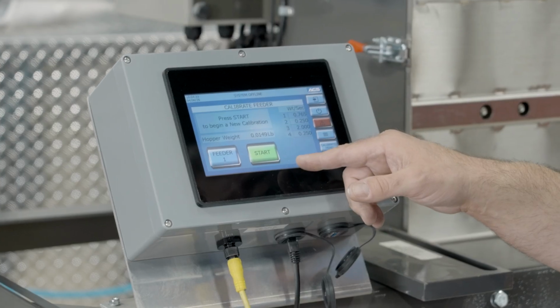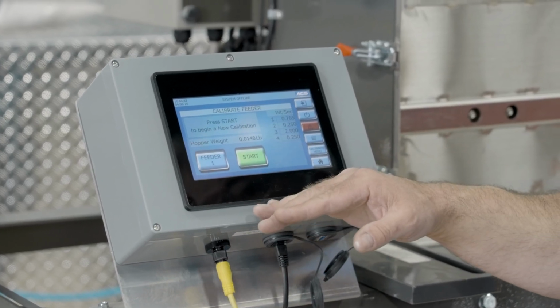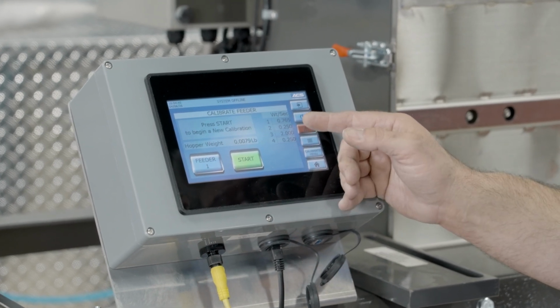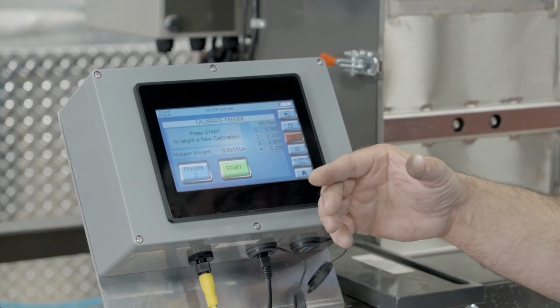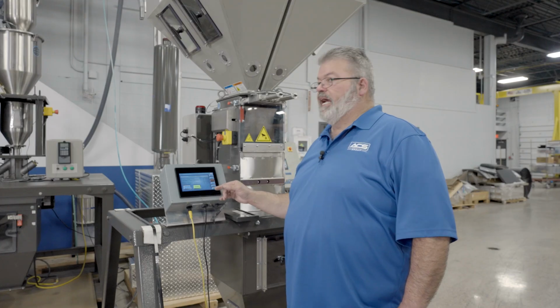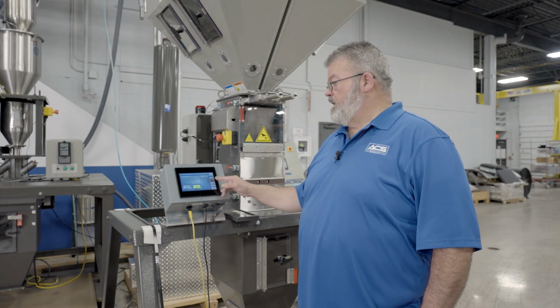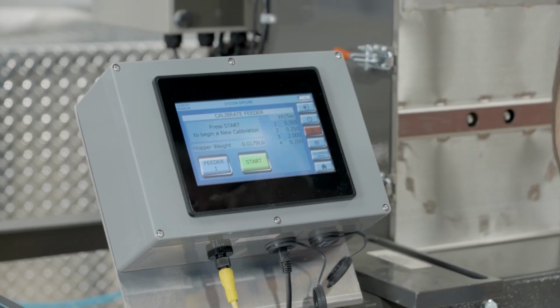That's how we basically determine how long to keep the gate open. So if we need to feed 1 pound out of hopper 2, we know we need to keep that gate open for 4 seconds. Every time we make a batch, we update that value, so you'll constantly see this value update as we're blending.